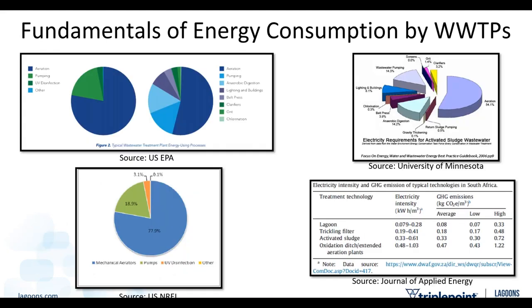On the screen here, these three pie charts, they all say basically the same thing. They say that something over 50% of the energy consumed in your system is being consumed by blowers, aeration. A large, large percentage, more than everything else combined, is being spent on blowers, on aeration. I'll call your attention to the chart at the bottom right, because I love this. This is out of the Journal of Applied Energy, by the way. It's a comparison of energy intensity and greenhouse gas emissions, and it compares different treatment strategies. I love that lagoons do it better, and they know it. They know that lagoons consume less energy per cubic meter of wastewater treated. They know that the greenhouse gas emissions are less with the lagoon system than any of its more energy intensive brethren. I love that little graphic there.